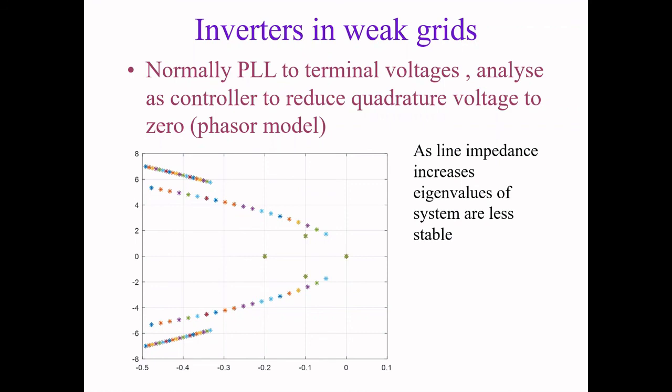voltage magnitude control is not the inner loop. The inner loop in most inverters is current control. The adjustment of the reference as an outer loop achieves a degree of voltage management. The same possibility exists here, that the inner loop is controlling the current to the broadcast angle, and then you have an additional term potentially to control voltage magnitude.